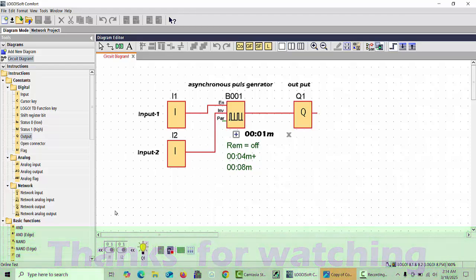So we will check this one. For example, now it's running as 4 seconds on and 8 seconds off. Now I give the signal for the second input, and now you can see this sequence is changed. Now 8 seconds will be on and 4 seconds will be off. You can see this is 8 seconds for on and 4 seconds for off. This is the function of this block.